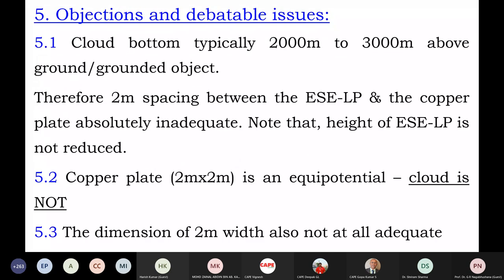Now, there are other objections to these experiments. I have raised only a few, there are many more. The cloud bottom in real life is 2000 to 3000 meters above ground or the grounded object. Of course, the grounded object is also the ESE or the Franklin rod. Therefore, 2 meters spacing between the ESE LP and the copper plate is absolutely inadequate, unthinkably inadequate. Note that the height of the ESE LP itself is 2 meters. And then how can 2 meters between the tip and the copper plate represent the height to the cloud? And then the electric field will be terribly different.